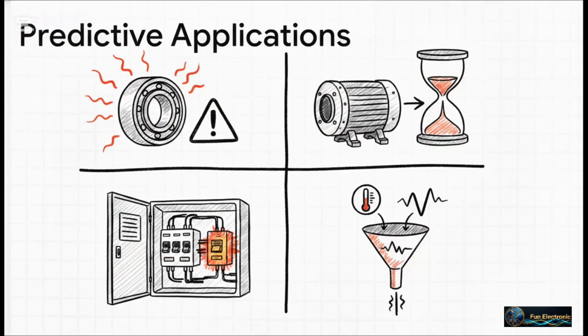This continuous data is really where the magic happens for maintenance teams. For instance, if a machine's bearing is running just 10 to 15 degrees Celsius above normal, continuous sensors instantly flag this as early lubrication failure or dangerous friction. For electric motors, the stakes are even higher. Every 10 degrees over their temperature class limit actually halves the motor's insulation lifespan.